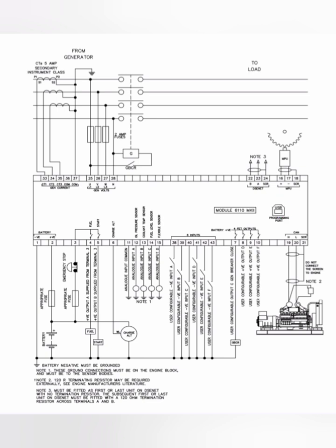And on the upper side, as you can see here, we have the generator inputs, and also we have the mains inputs. And the last one, as you can see here, we have the MPU inputs and negative. On the upper side, 16, 17, 18 are the MPU inputs. And as you can see here, we have programmable ports. This is the complete installation method of the Deep-sea PLC controller, all types.